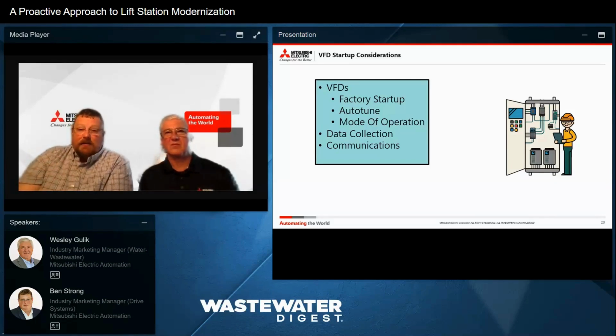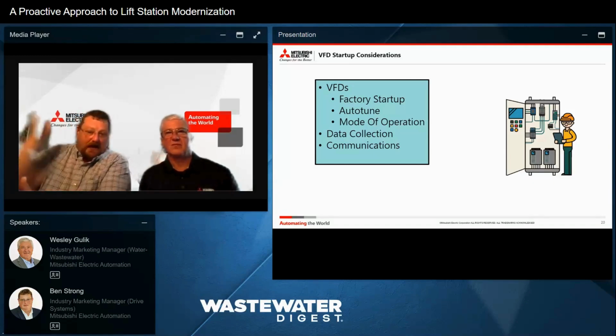Things to think about on data collection: how is the data going to get up to upper-level control? How am I going to collect data and then make it useful? There are schemes where I have a VFD, I have a PLC, I take the data to the PLC, and then I collect it, aggregate it, and push it up to the SCADA system. But with most VFDs, you can have it connected to a PLC and to the SCADA system, so you can choose that rate.